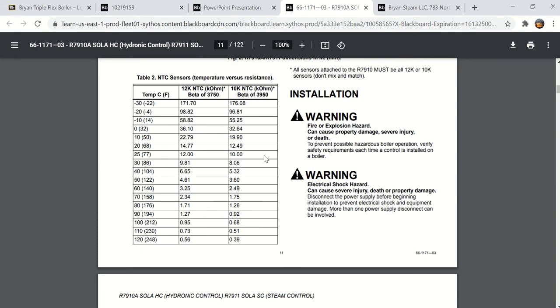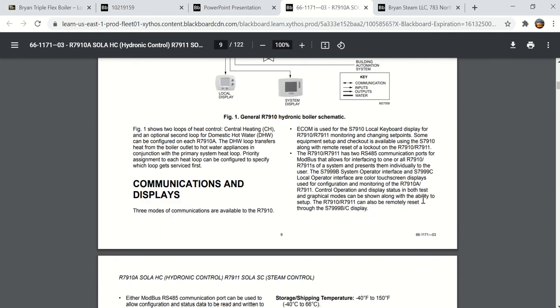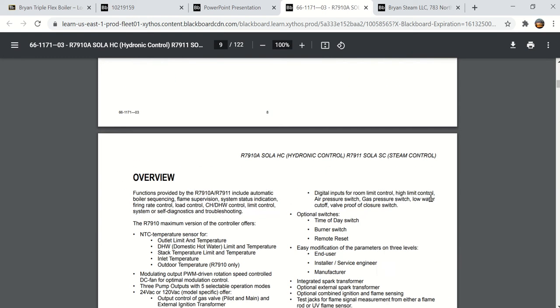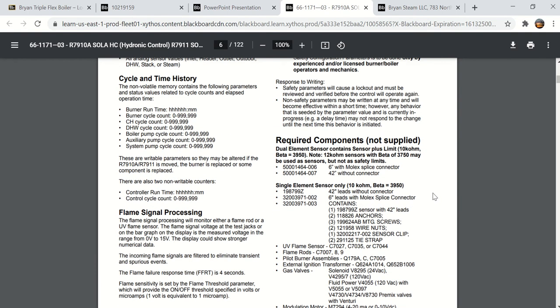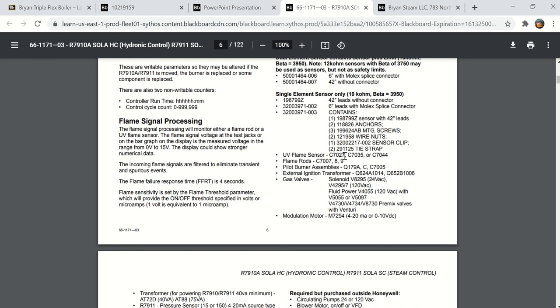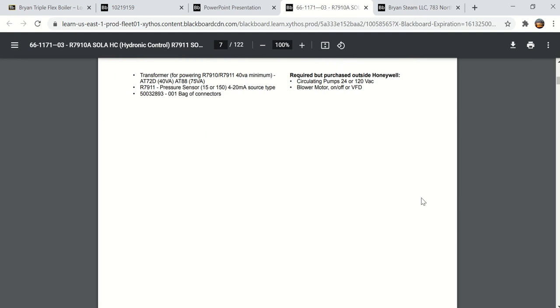Positive temperature coefficient means that as the temperature goes up, the resistance goes up. If it's negative, it's the opposite. As the temperature goes up, the resistance goes down. That's the difference between PTC and NTC. So there was your sensor part numbers if you need that. Here's a scanner, UV scanner, certain flame rods that Honeywell makes.